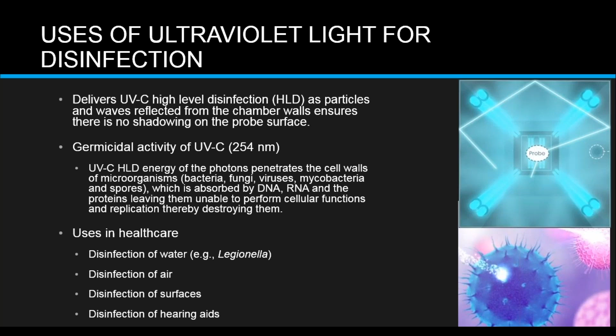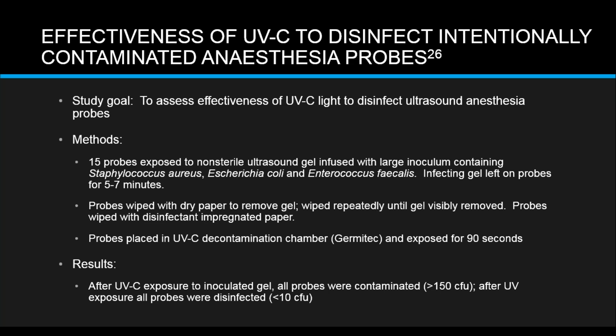I'm going to start showing you some studies here to assess the effectiveness of UVC light to disinfect ultrasound anesthesia probes. 15 probes were exposed to non-sterile ultrasound gel infused with a large inoculum containing relevant pathogens. The gel was left on the probes for 5 to 7 minutes, then it was wiped off. Probes were wiped with a disinfecting impregnated paper and placed in a UV chamber. So here they were intentionally contaminated with very large numbers of pathogenic bacteria and exposed only for a minute and a half. After exposure to inoculated gel, all probes were contaminated, but after UV light, all the probes were disinfected with less than 10 colony-forming units.